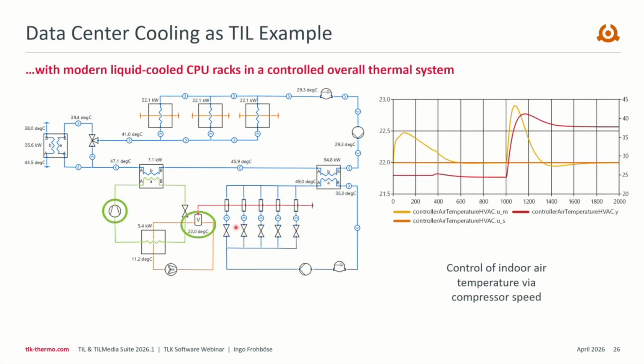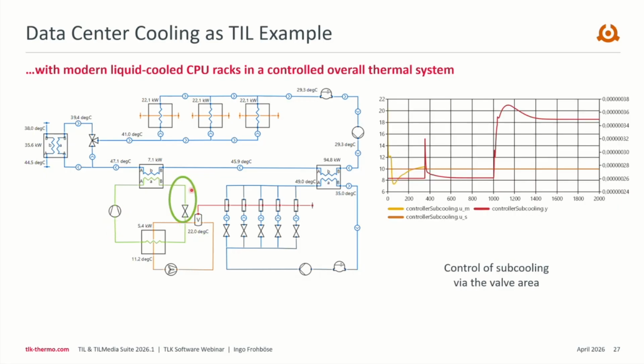Then we control the air temperature in the room with the compressor speed of the air conditioning system, and we control subcooling with the TXV, or the valve area.